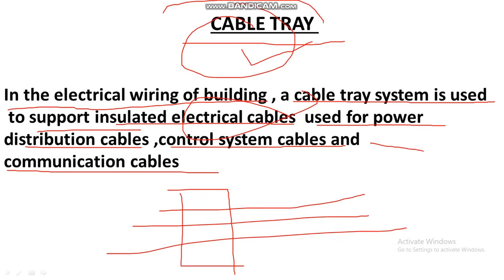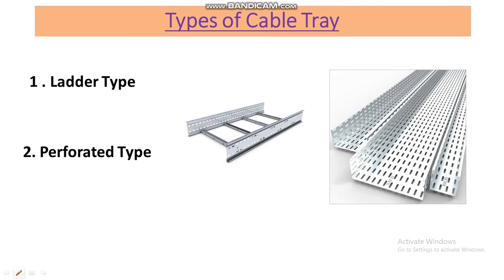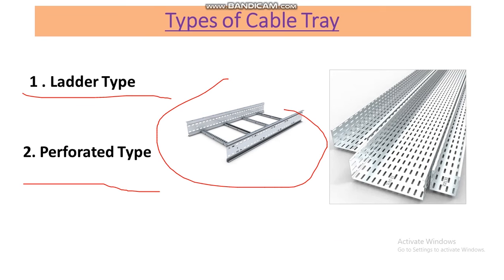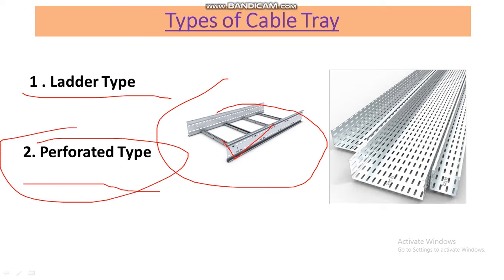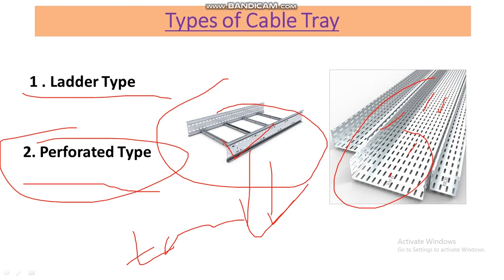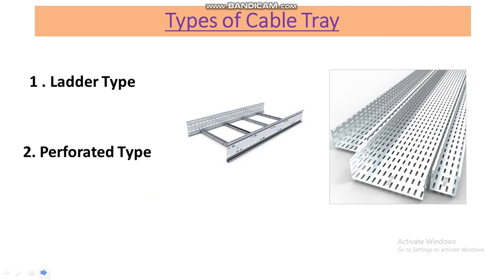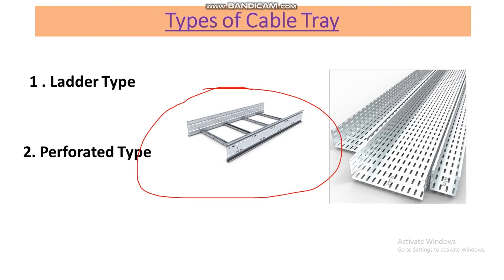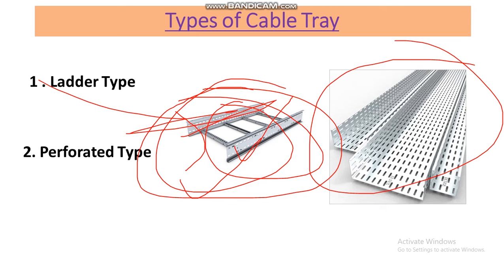Now, there are two types of cable tray: ladder type and perforated type. The ladder type looks like a ladder, and the perforated type has small multiple holes. The ladder type is used for long spans and where more heat needs to be dissipated from the cable. If you have more heat dissipation requirements, use the ladder type; for lower heat dissipation, use the perforated type.